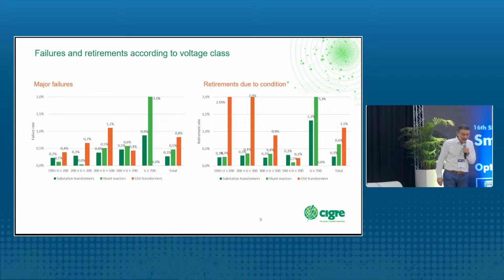So if we go to the failure rates, on the left graph we can see the rate of failures. You can calculate this rate of failures if you divide the number of major failures by the number of transformers which are operating, multiplied by the time of your investigated interval. We investigated failures between 2010 and 2019, so 10 years, and we had to multiply this by the number of transformers, 40,000 transformers in our database. So we have basically 500,000 transformer years as operating experience and a little bit more than 1,000 failures. And this brings us to an average failure rate of 0.3%, something like that. So it's quite a low value.